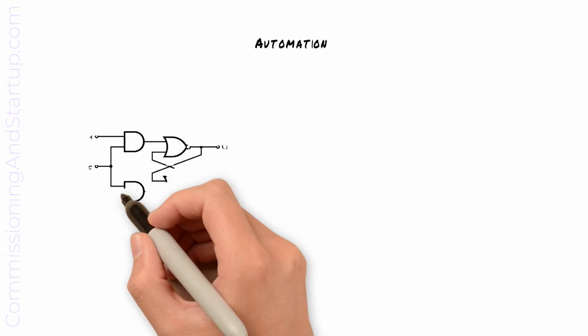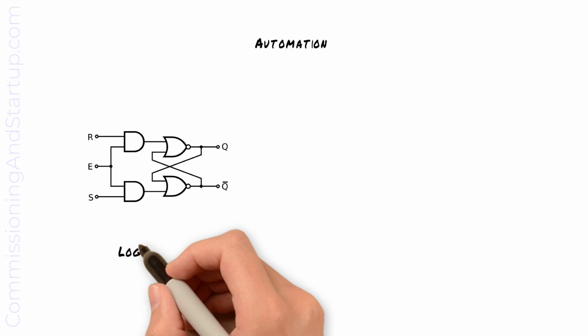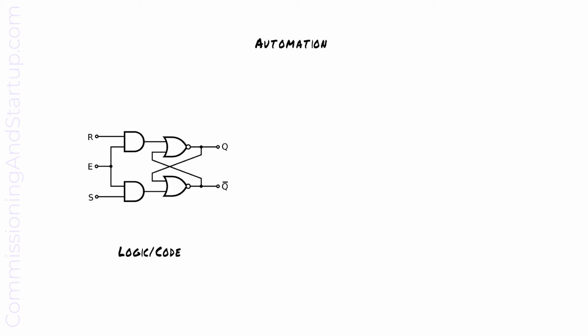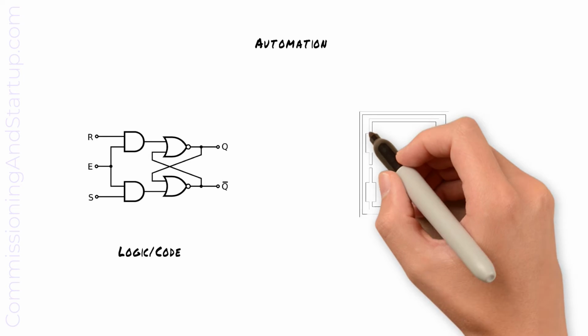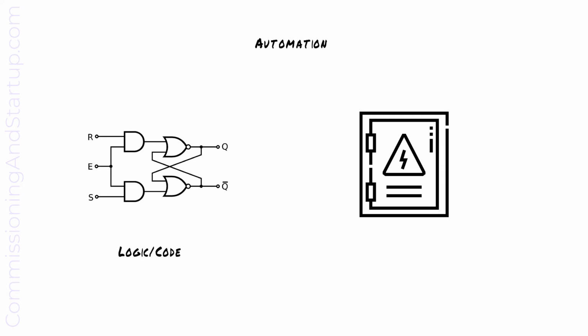Software is an important part of factory acceptance testing to verify that the automation, logic and code is programmed correctly per specification. Software should be uploaded to the hardware and integrated factory acceptance testing conducted to ensure that the hardware and software function correctly per specification.